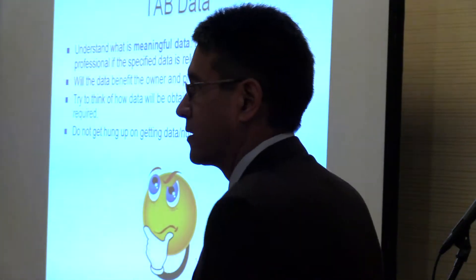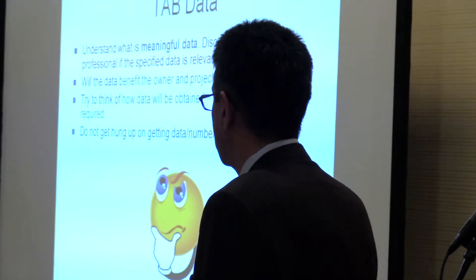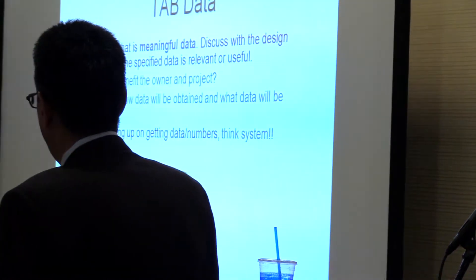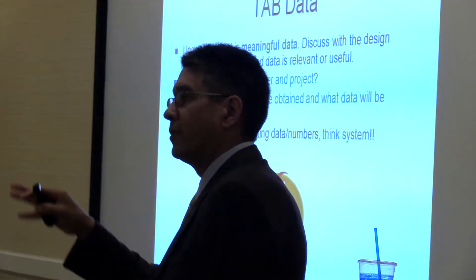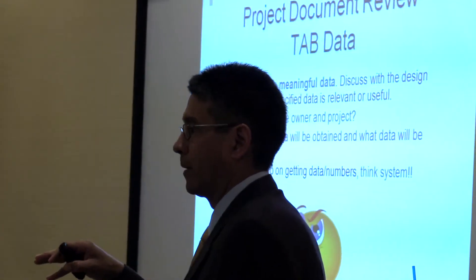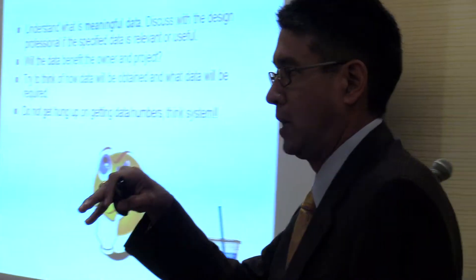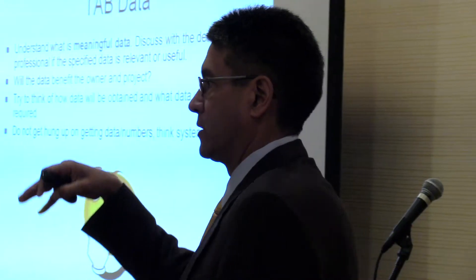How is it performing? Is it meeting design intent or not? We always say don't get hung up on the numbers — think system. If I'm not getting my design airflow into this room, think system-wide.